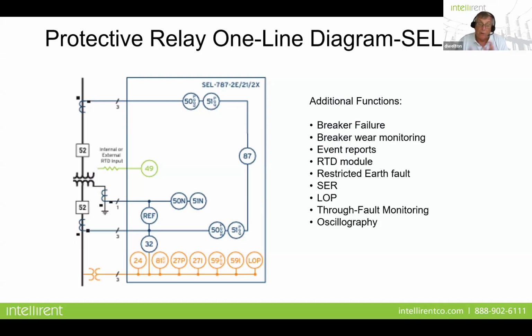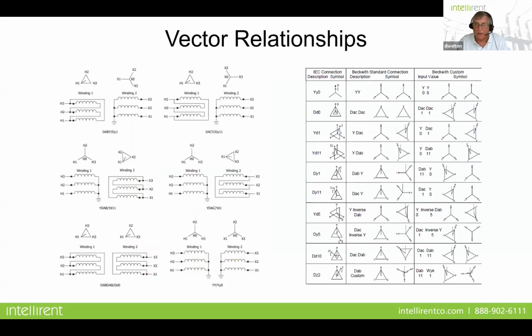When I worked for a relay manufacturer, whenever there was an event or a trip that occurred, they'd immediately call our tech support, and the first question out of their mouth was, "Did you save the through fault oscillography? Did you save the oscillography in the sequence of events? Could you send it to me?" And if they said, "Well, no, we didn't have either of those two things enabled," well, guess what? There's nothing I can do to really help you decide what it was that happened during that event.